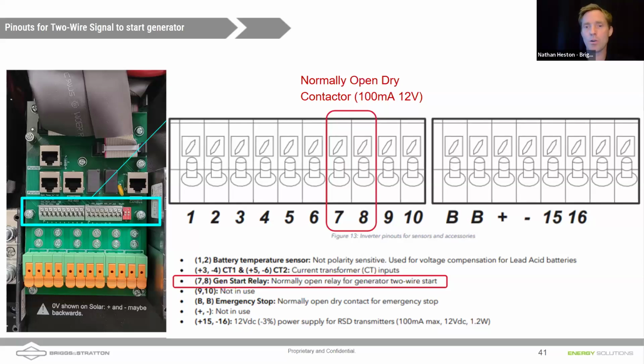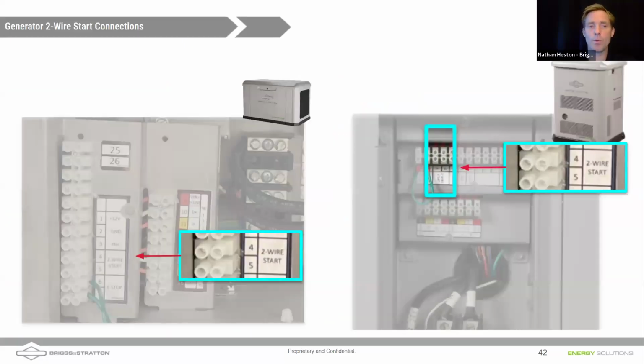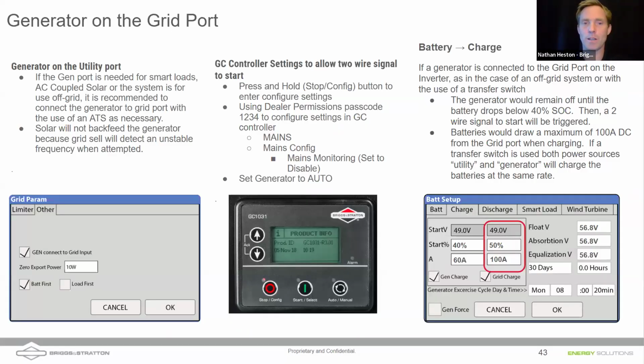And so it'll either pass current through a loop or it won't. So that dry contactor can be wired into pins 4 and 5 on either our 26K or our 13K generator that you can see there, or any of our two-wire start generators. And that'll allow the inverter control of that generator. We do need to disable something though, Daniel, right? What do we have to disable on our generator in order to use two-wire signal start?